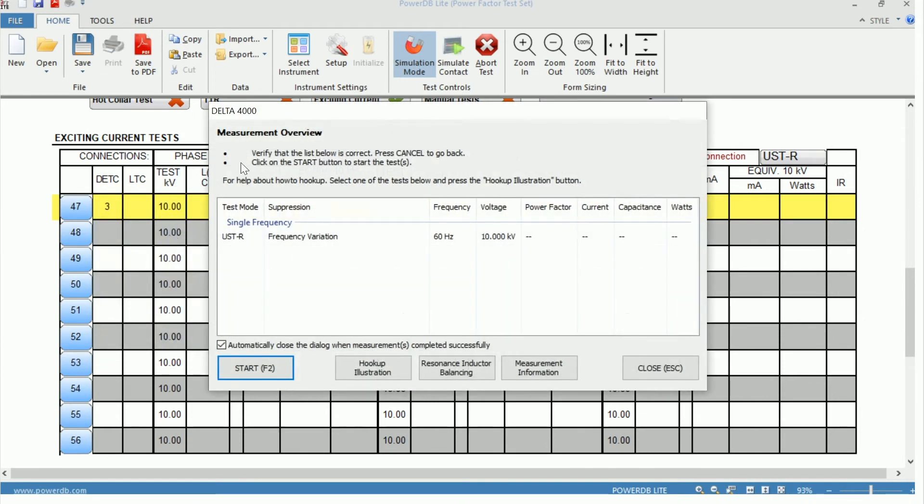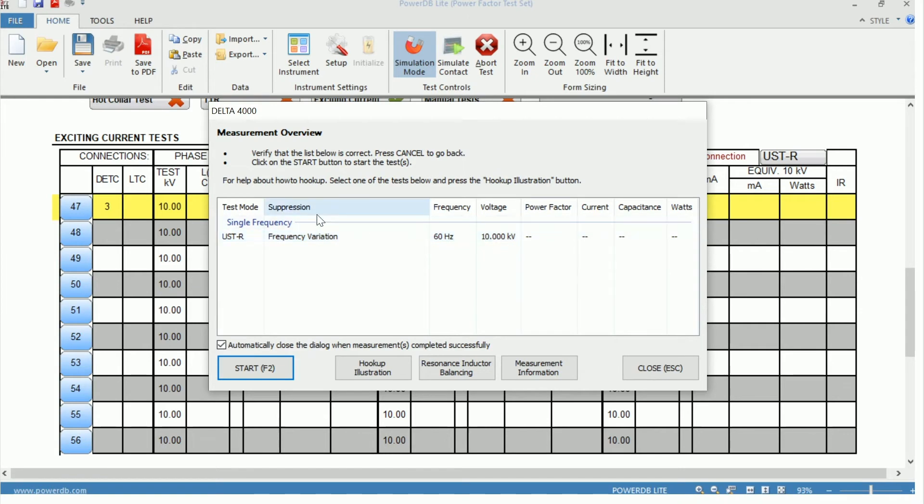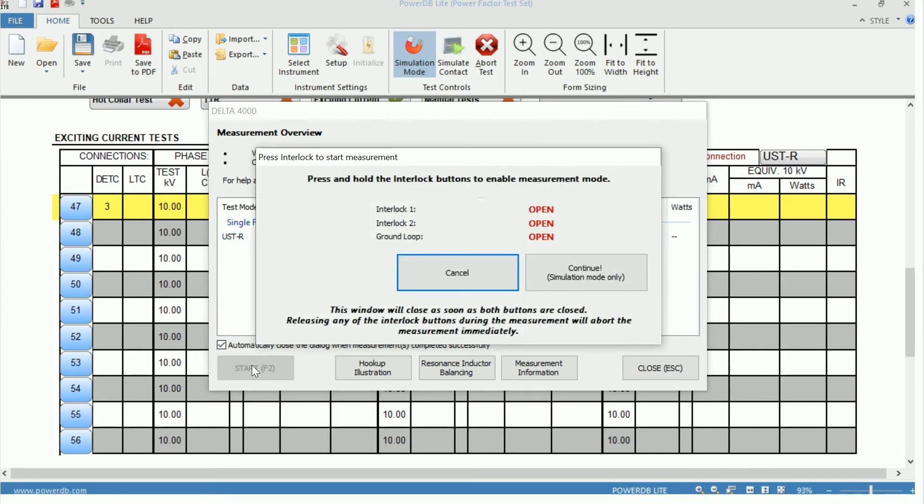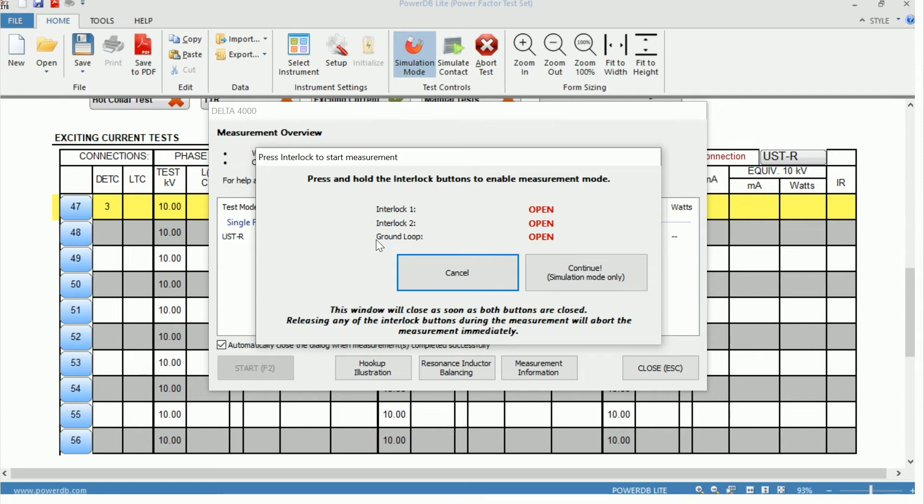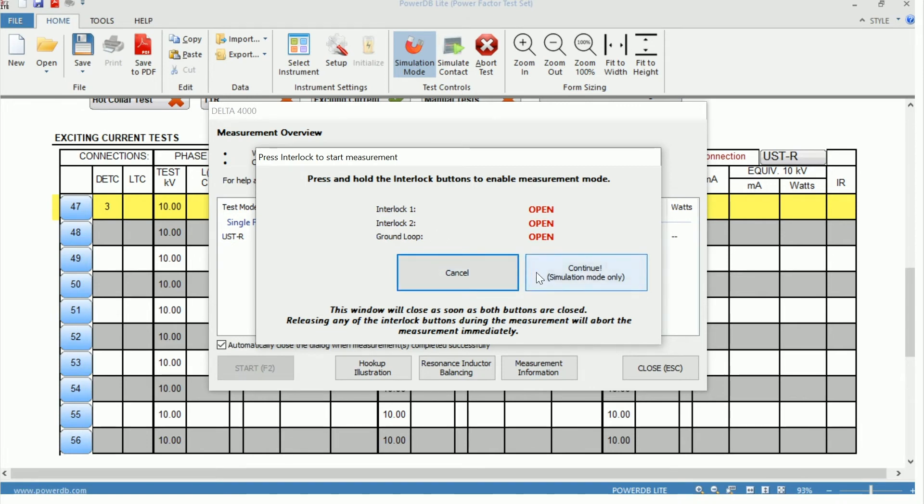Here we have our measurement overview, where we have our test mode, the suppression method, our test frequency, and our test voltage. We can go ahead and continue with the measurement. And up pops interlocks and ground loops. So when performing a test with the Delta 4000, it's imperative that these three conditions be met to move forward with the testing. And that's that both interlocks must be depressed and the ground loop must be closed. So the LED on the side of the Delta 4000 should be off. For the purpose of this, we'll move forward in simulation mode.